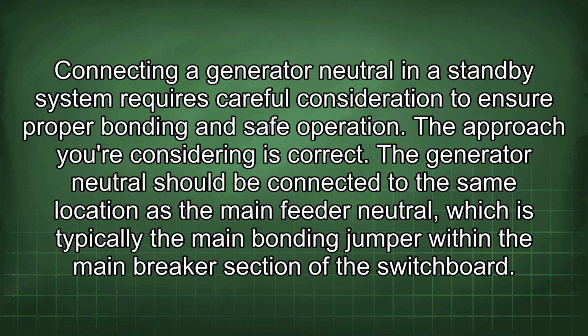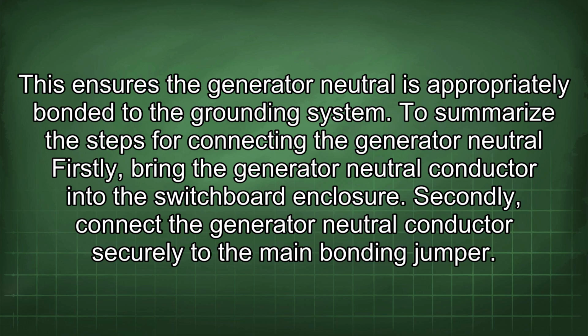Connecting a generator neutral in a standby system requires careful consideration to ensure proper bonding and safe operation. The approach you're considering is correct. The generator neutral should be connected to the same location as the main feeder neutral, which is typically the main bonding jumper within the main breaker section of the switchboard. This ensures the generator neutral is appropriately bonded to the grounding system.